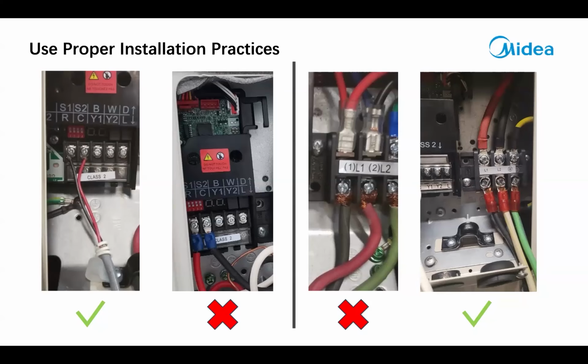When you do those connections, we don't like multi-conductor unshielded stranded. So if you're going to use the existing thermostat wire, pick the two wires that you're going to use, and snip the rest of them off back at the outer jacket. If you have communication issues, there's one thing you can try: take your extra conductors, twist them together, and ground them at one end, like you do the shielded cable. Sometimes that will help with the interference. But it will work with standard wire, so it will work, yes.